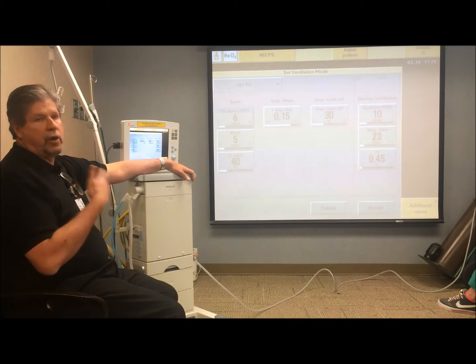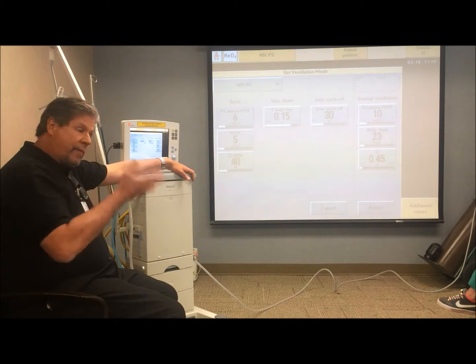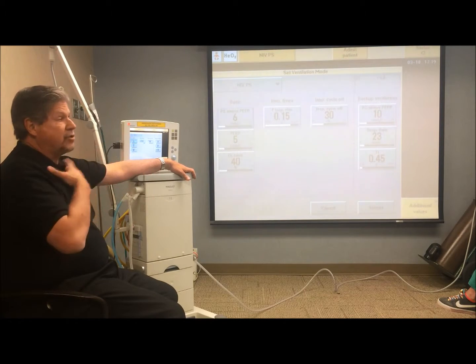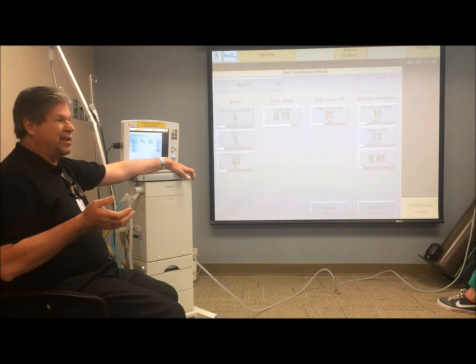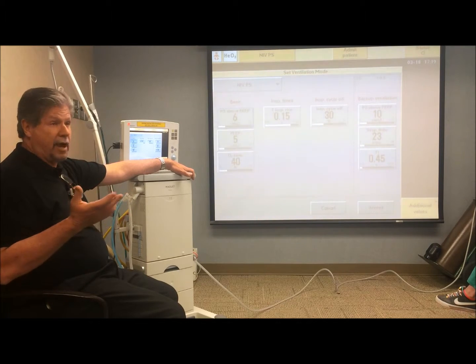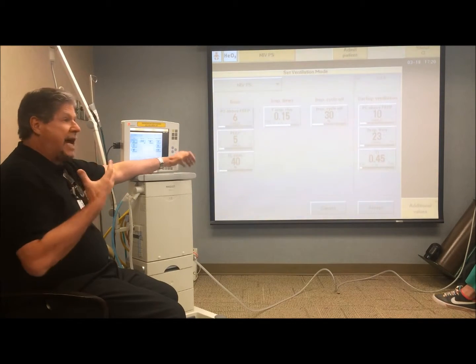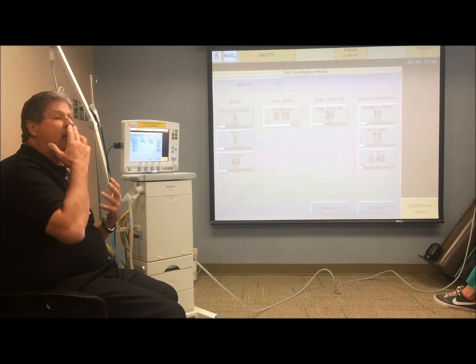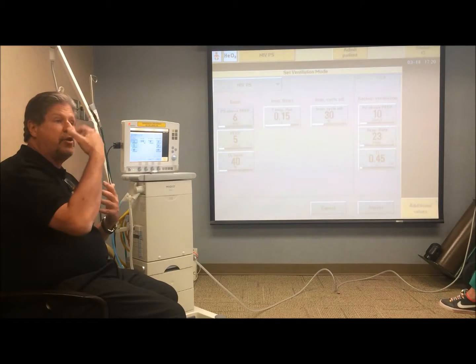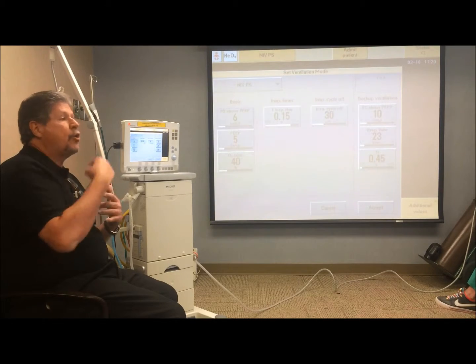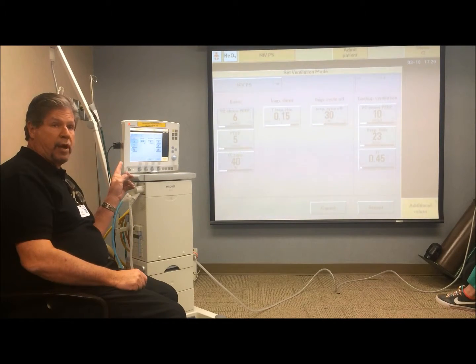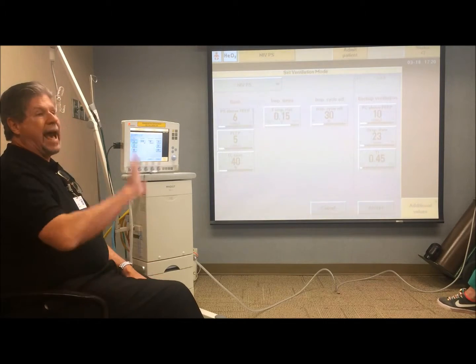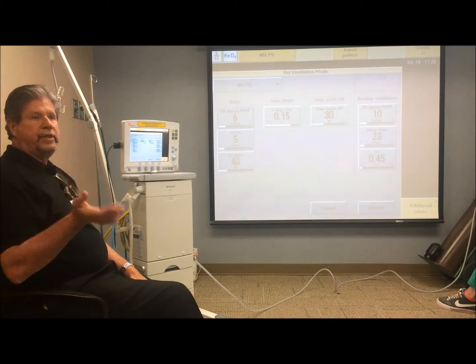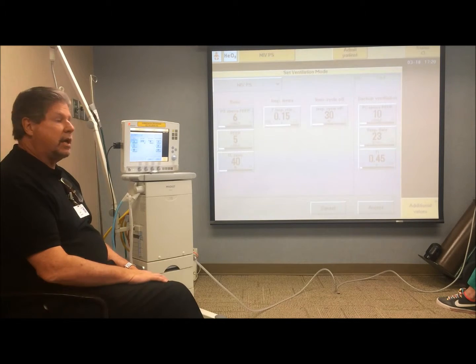So, the therapist would say, Jim, this isn't working, the ventilator's always going to backup, and I said, well, remember I told you that this was really only intended down to 3 kilograms, and actually, speaking as a respiratory therapist, I would say that we probably should say more like 5 kilograms, because you would need a good sized kid that had a good strength that could overcome the leak and still transmit a pneumatic signal back to the ventilator in order to trigger the ventilator into pressure support breaths. So this mode was out in terms of using it for ventilating a 1 kilogram kid.